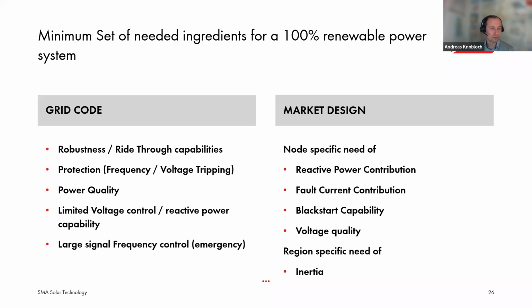Here, this slide shows, from our perspective, what should be defined in a grid code and what should be defined by market design. In a grid code, of course, a minimum level of robustness and ride-through capabilities are necessary. This is inevitable to achieve a stable power system. Also, protection and the settings of this protection are very important. Minimum levels of power quality, limited voltage control, and reactive power capability that is needed for power feed-in, and of course some requirements on large signal frequency control in emergency situations, like the LFSM mechanisms for over and under frequency, for example.